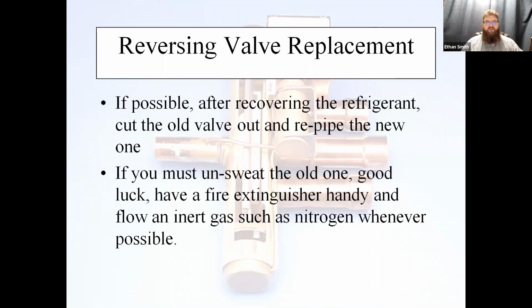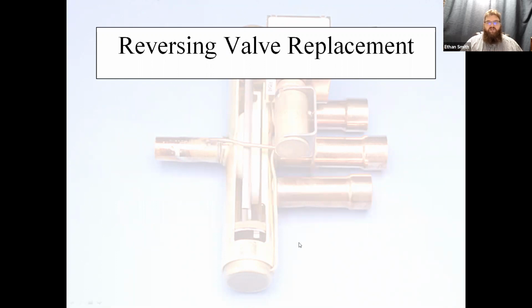If you don't, you're going to introduce copper oxide buildups inside the pipes. And I'll tell you where that copper oxide is going to build up, guys, is right in your capillary tubes on your pilot valve. And pretty soon you're back changing another reversing valve because it's contaminated now. So make sure you're flowing nitrogen all the time.